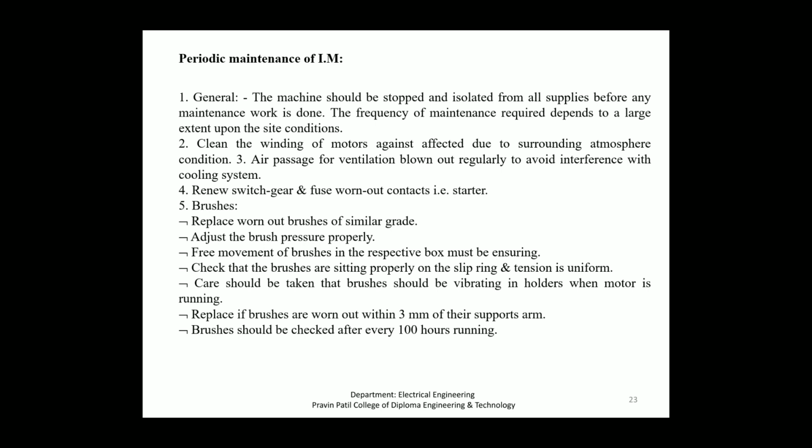Next, the brushes. Replace worn out brushes with similar grade. Adjust the brush pressure properly. Then the free movement of brushes in the respective box must be ensured. Check that the brushes are sitting properly on the slip ring and tension is uniform.